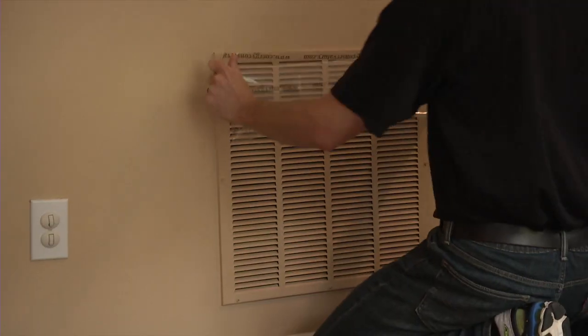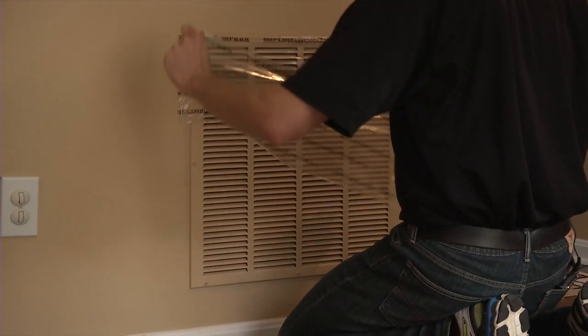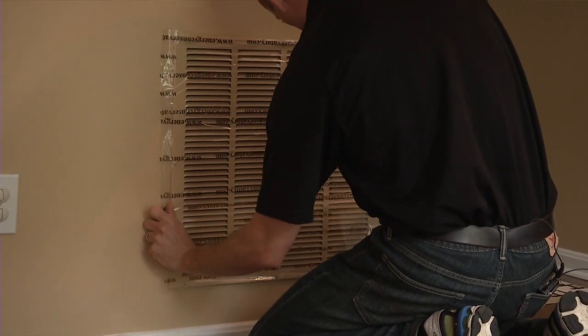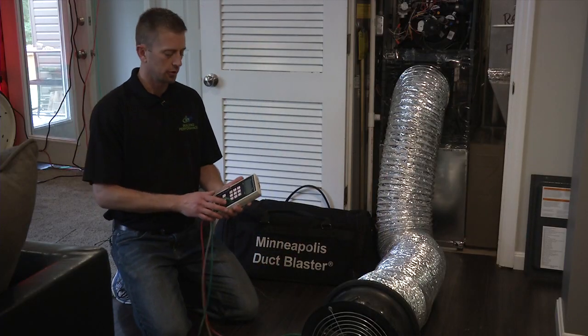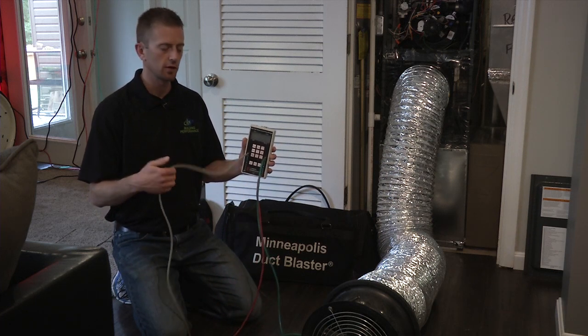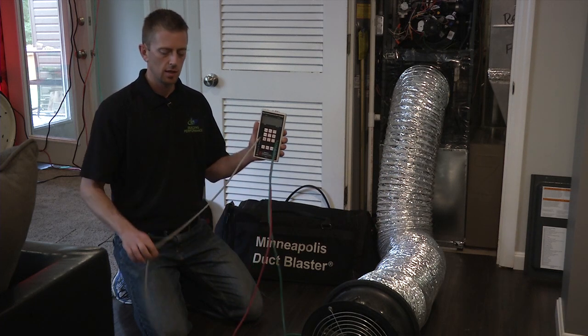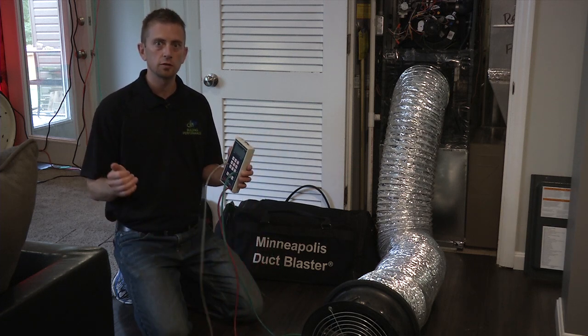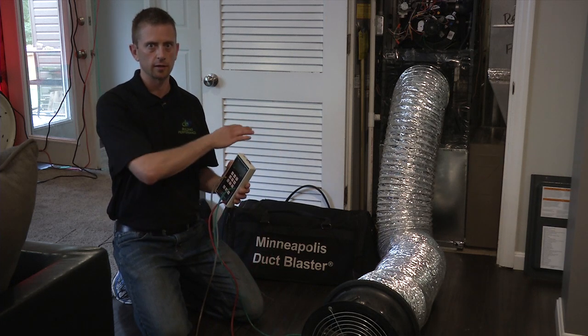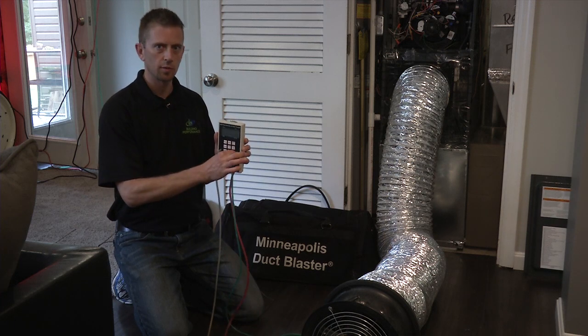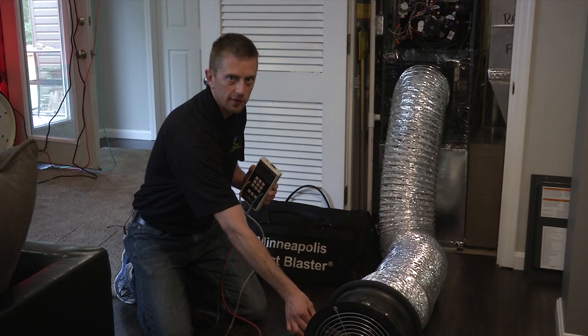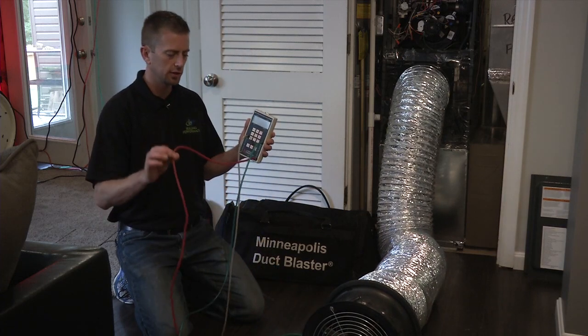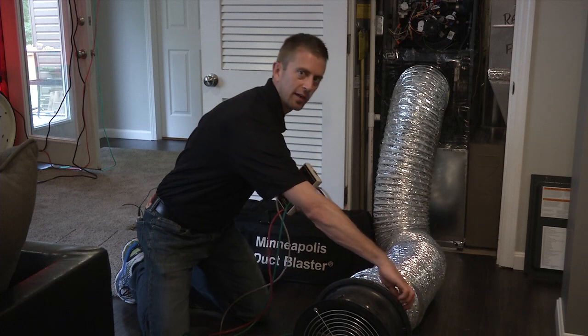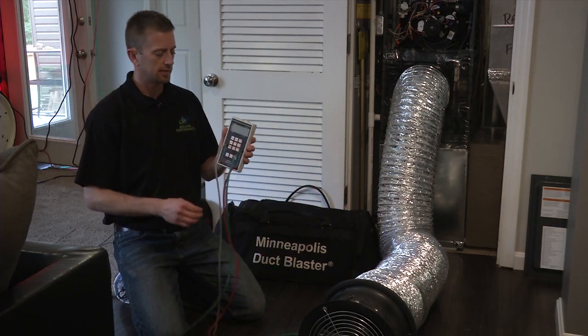So now that we've got the house set up for the test, with all the ductwork sealed off and covered, I'm going to get the gauge set up for the duct blaster and baseline it. If you're using a Minneapolis blower door, you're going to want to put your clear hose, which is your reference hose, on the upper left-hand tab. This clear hose is going to go into the closest supply register that you can find to the air handler. The green hose goes in the upper right. It connects to the brass tip on the side of your duct blaster. And then the red hose goes on the back side of the fan. It catches the airflow there. So that's how it's set up.